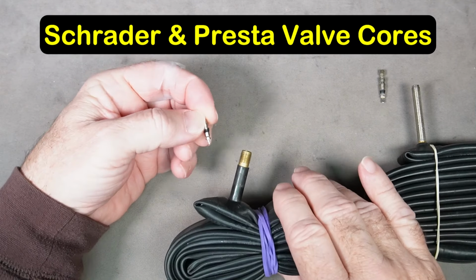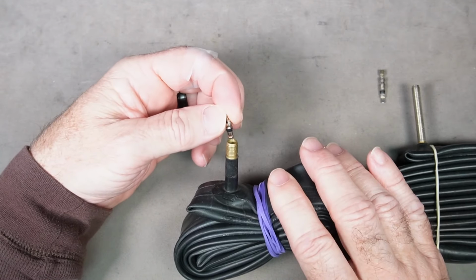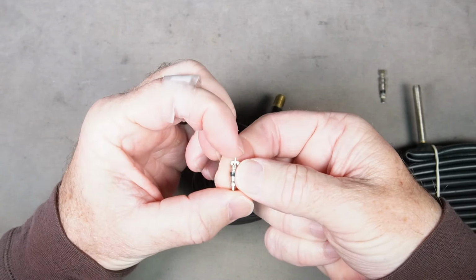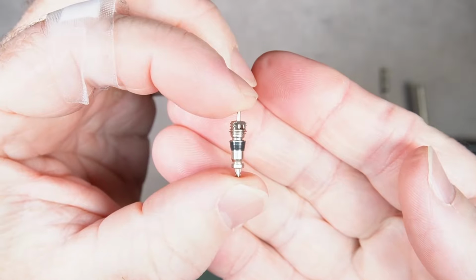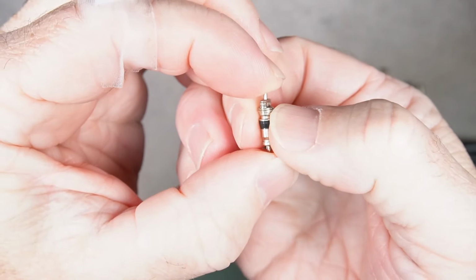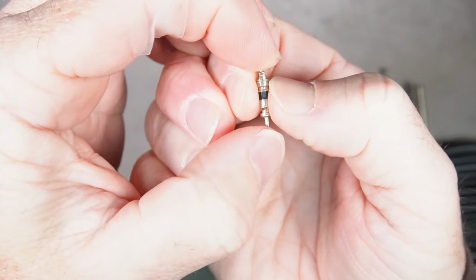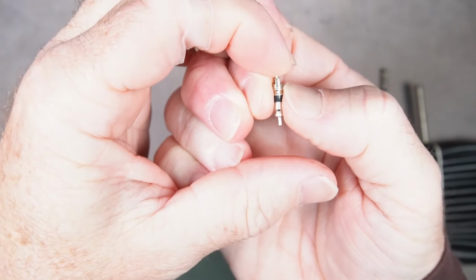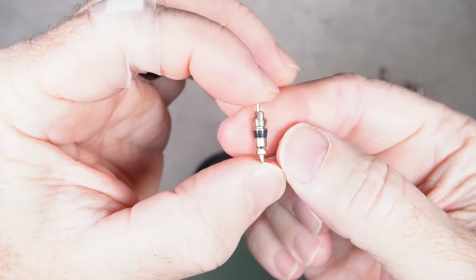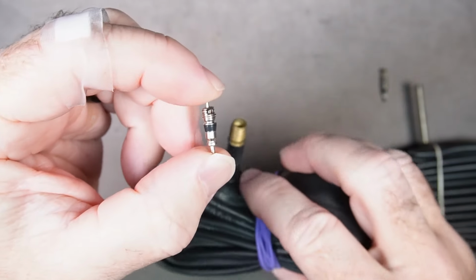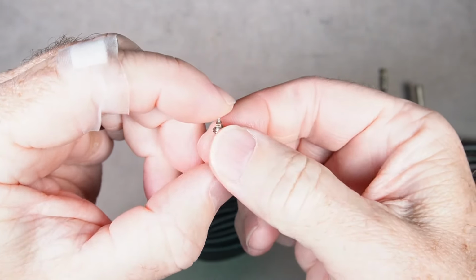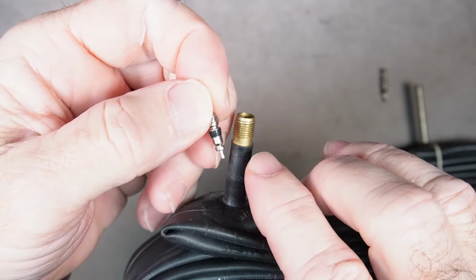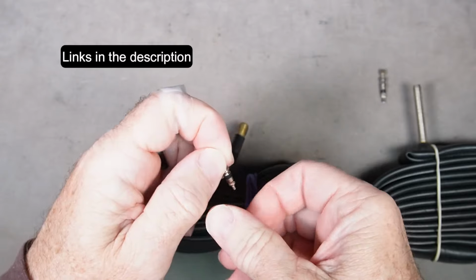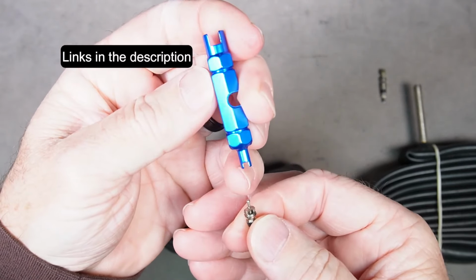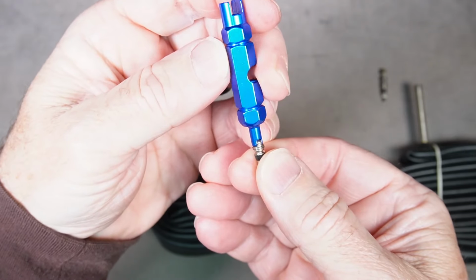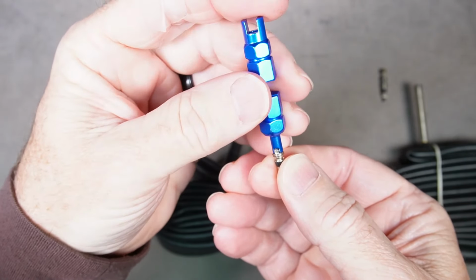All right, let's talk about valve cores. So the core of a valve is simply the workings of the valve, which is down inside. This is really what makes the valve work. This is a Schrader valve core. It's got a spring in it so that when you press on that pin at the top, the bottom opens up and lets air flow. So that's what a Schrader core looks like. Most Schrader cores are replaceable. If for some reason the valve doesn't close or the valve gets damaged, you don't always need to replace the entire valve or the tube. You can just replace the core. And there's a core removal tool, which looks like this, which reaches down inside, grabs a hold of it, and you can unscrew it or screw it back in with this tool.